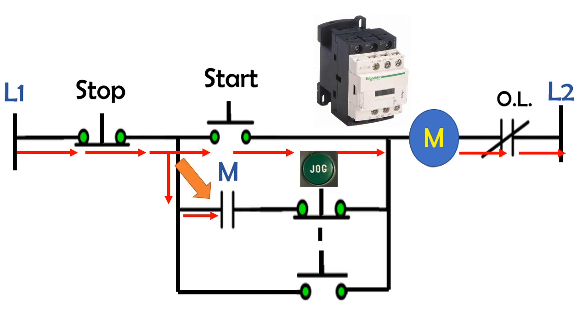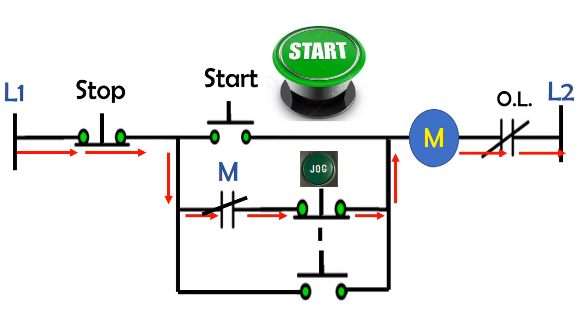When you release the start button, the current flow will divert from line one through the stop pushbutton, through the normally closed auxiliary contact, through the normally closed jog contact, through the magnetic coil and overload relay, then back to line two.